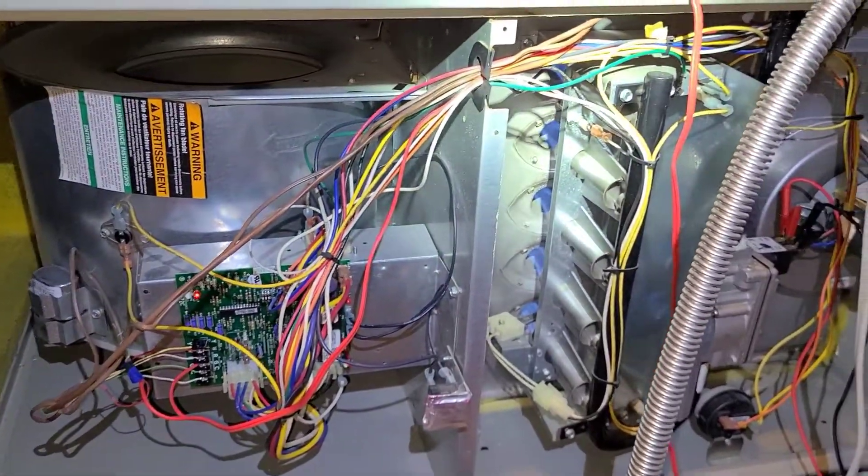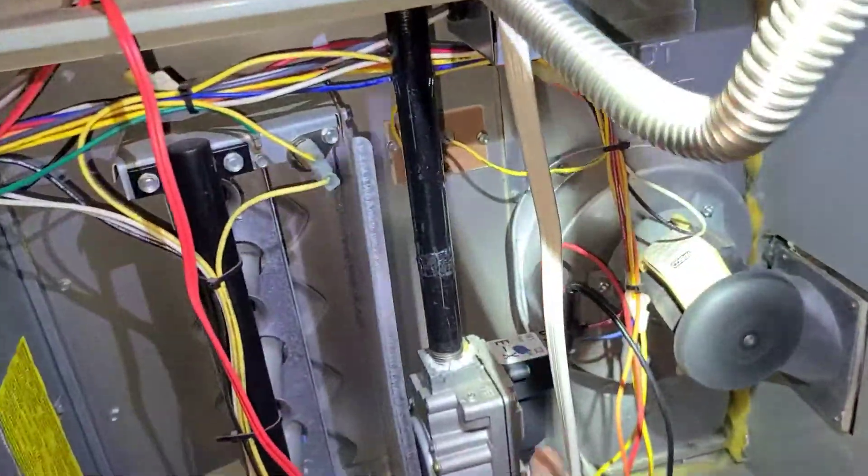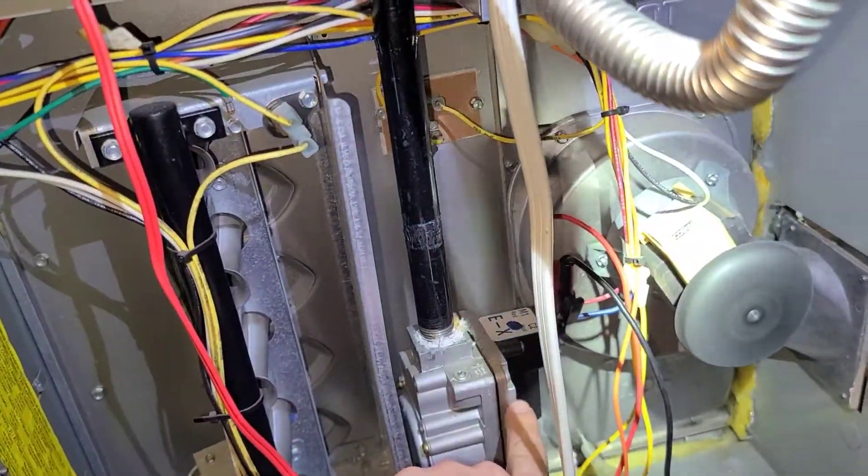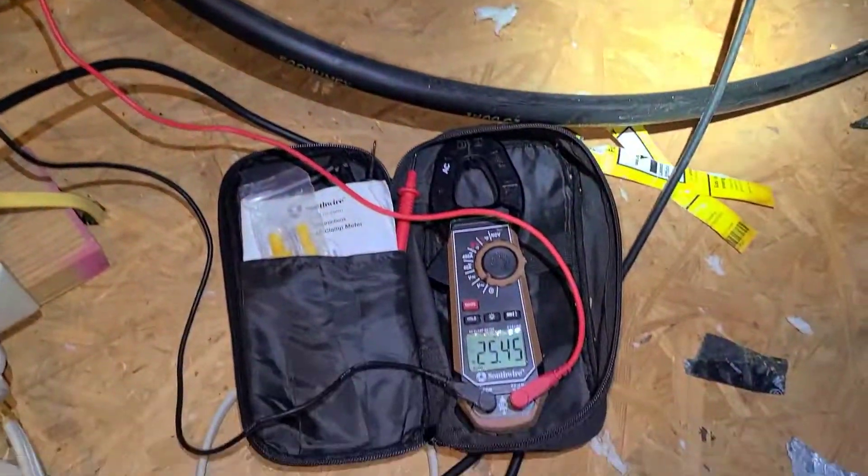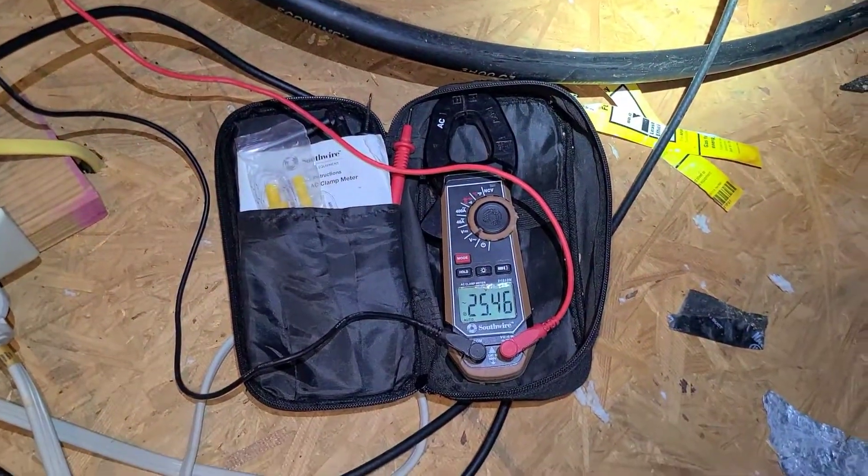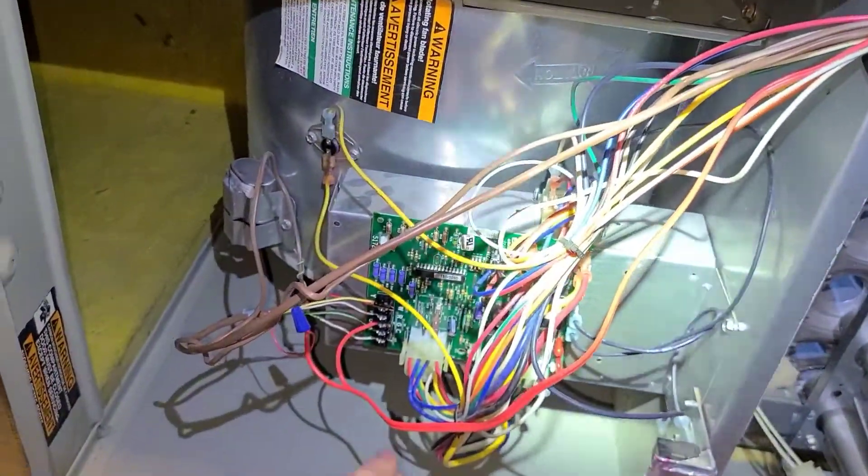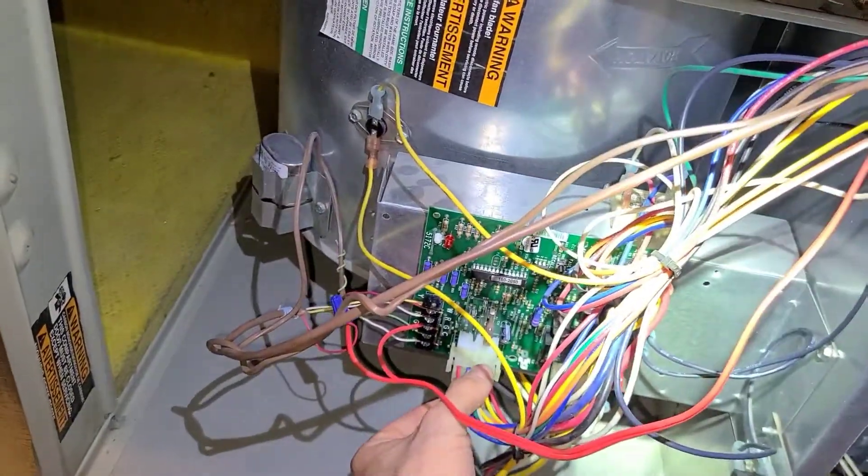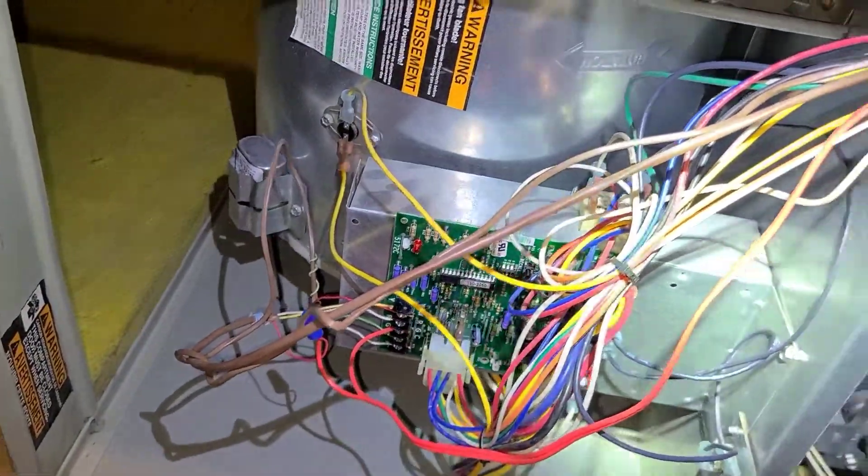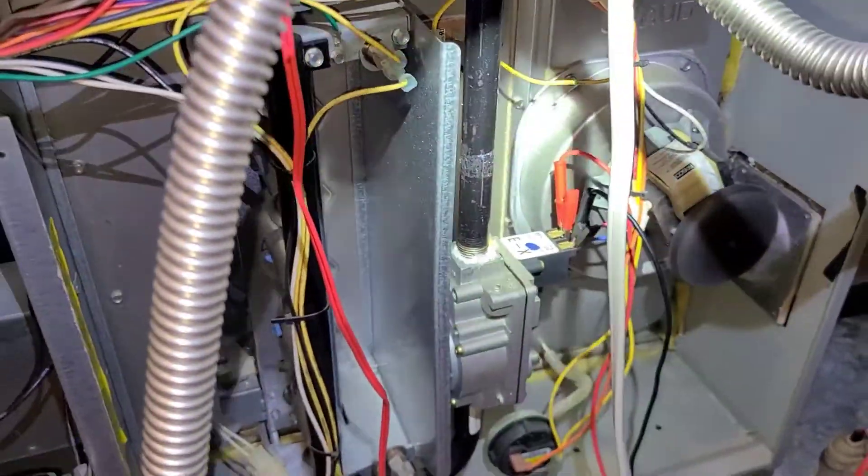As you can see, I do have 24 volts. The control board had 24 volts at the prong connector but was not sending 24 volts here, indicating a bad control board. Changed out the new one, unit is working now.